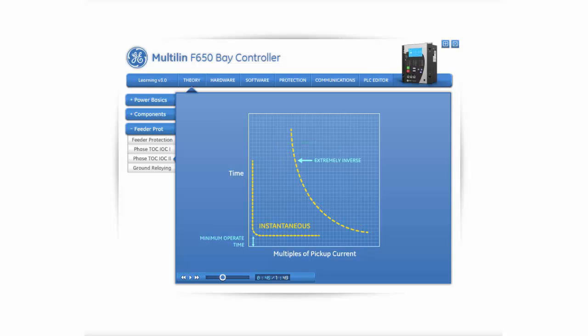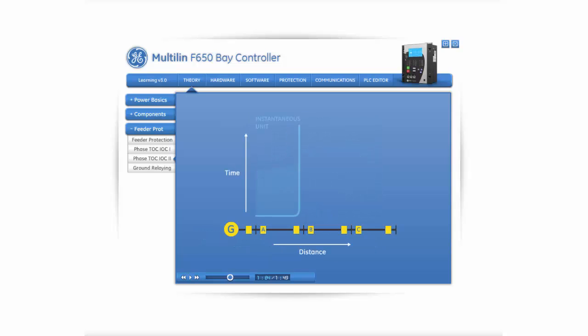During the selection of the curve, the protection engineer will be able to use a time multiplier to effectively shift the curve up or down on the time axis, in addition to a scaling adjustment to normalize the curve to the desired pickup level. That is to say that the pickup will be equivalent to 1 per unit, or 100% on the x-axis. The setting of a series of coordinated time-overcurrent relays on a feeder or distribution circuit begins at the point farthest removed from the generating source. As the relaying is set and coordinated back toward the generating sources, the time required to clear a fault becomes longer as the source is approached.